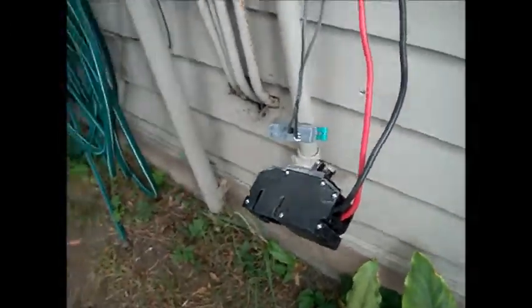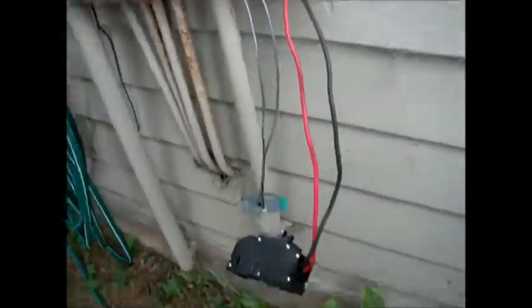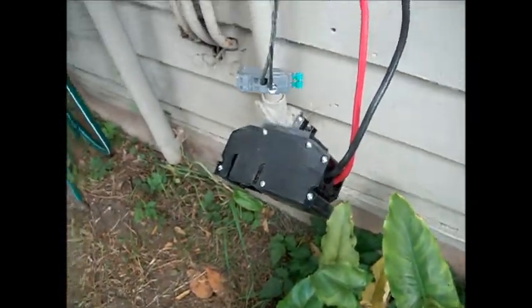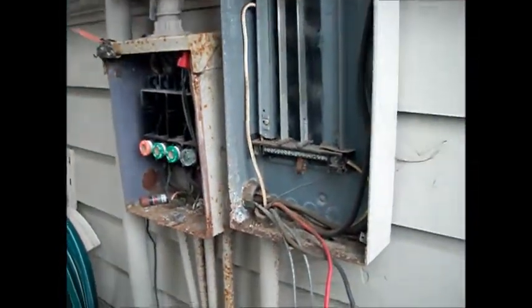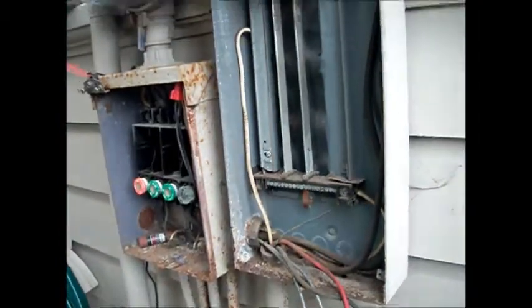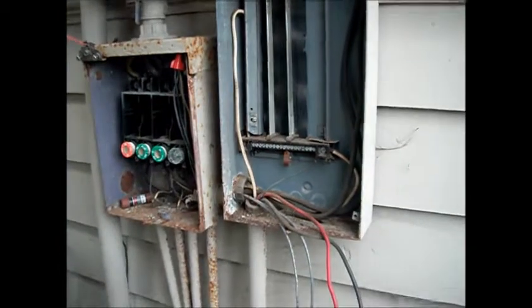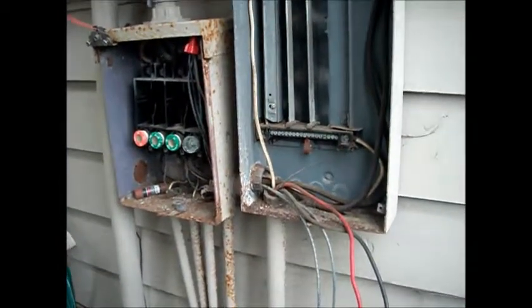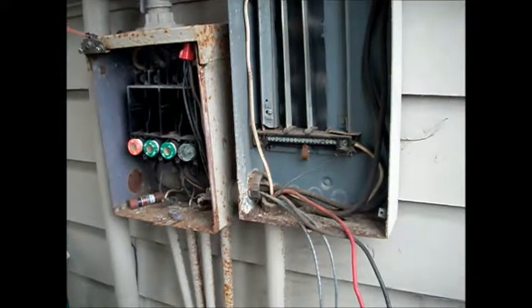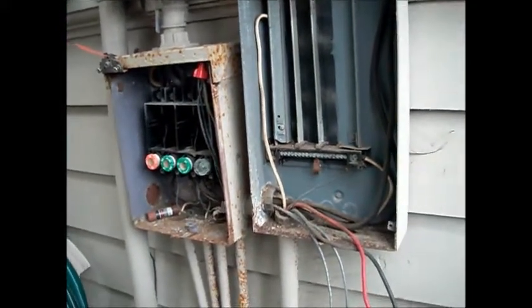That's why we lost power. This situation may happen with your dryer or your range — it may have only partial power. For instance, your dryer may come on but it might not heat. Or your range may only have two burners on opposite sides that work, or your main oven burner may not work.